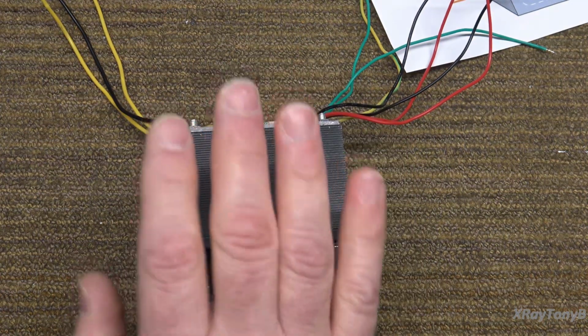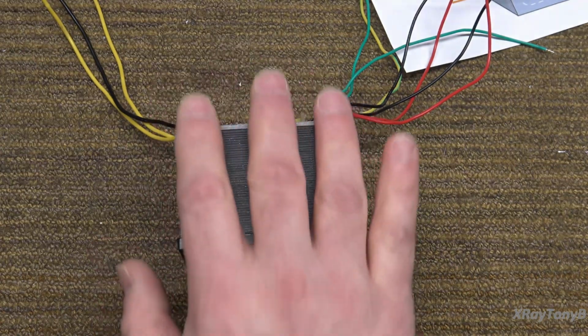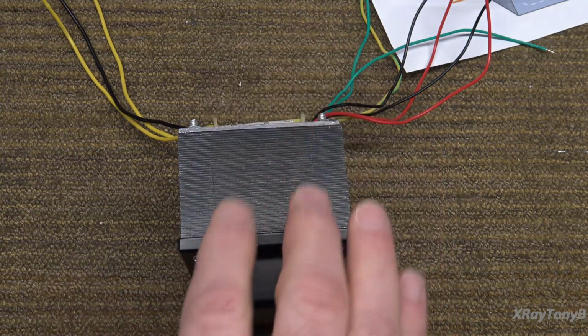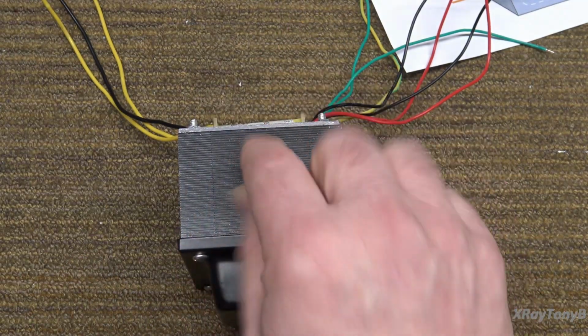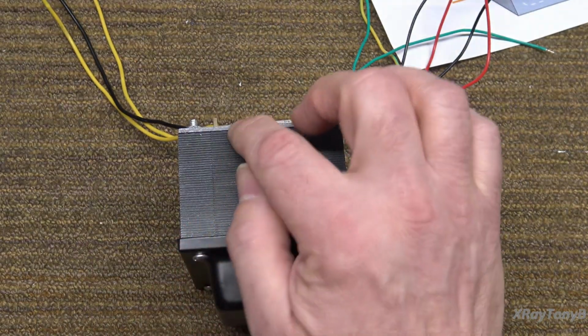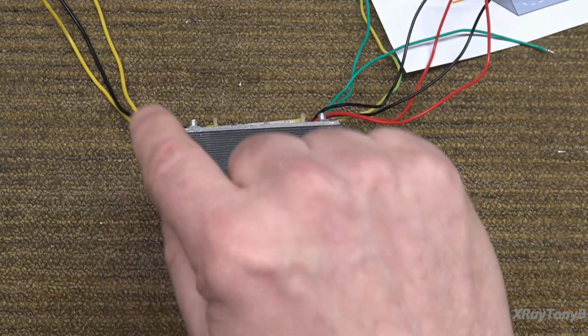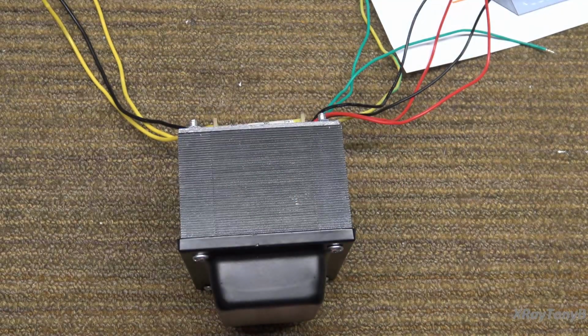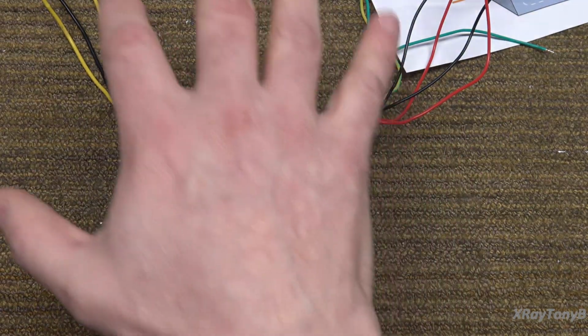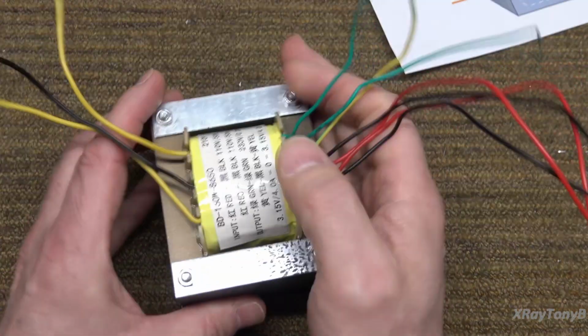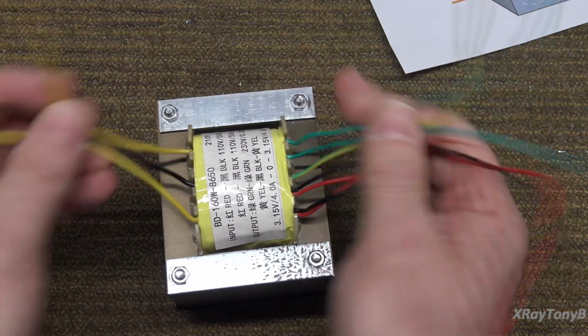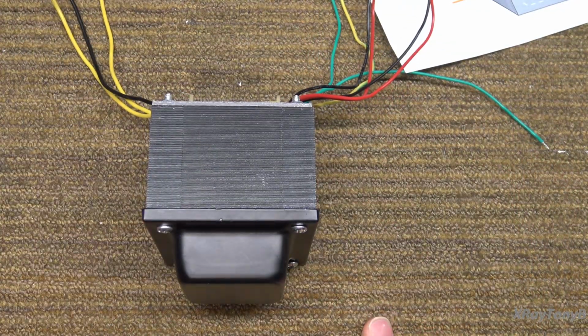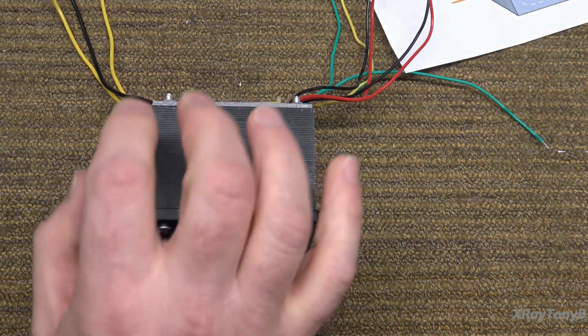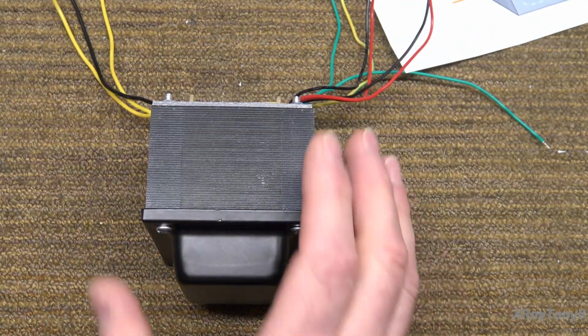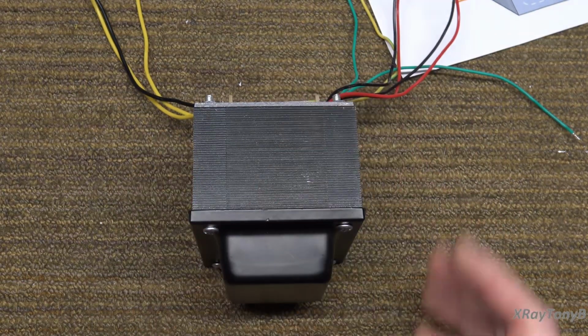However, if we tried to put anything real high frequency, in the hundreds of kilohertz or even tens of kilohertz, it would never be able to magnetize to its highest potential because it's taking too long - by the time it starts to magnetize, your AC waveform's already dropping and reversing direction. So you won't have a good magnetic field building and collapsing, that changing field needed for inductance between the primary and secondary. You have to use the correct material for your transformer based on the application, and that's what controls the size of the transformer, its metallic formula, and its properties.